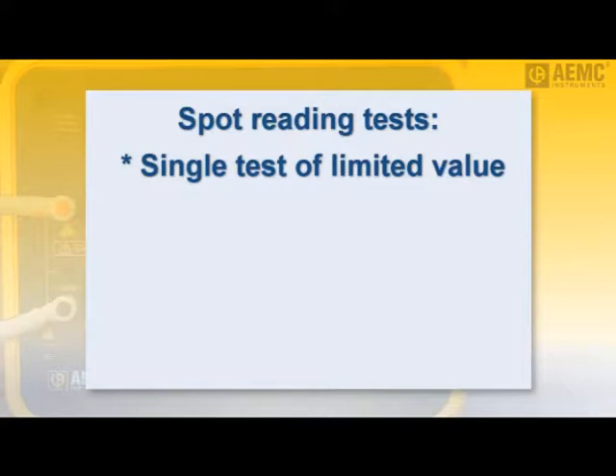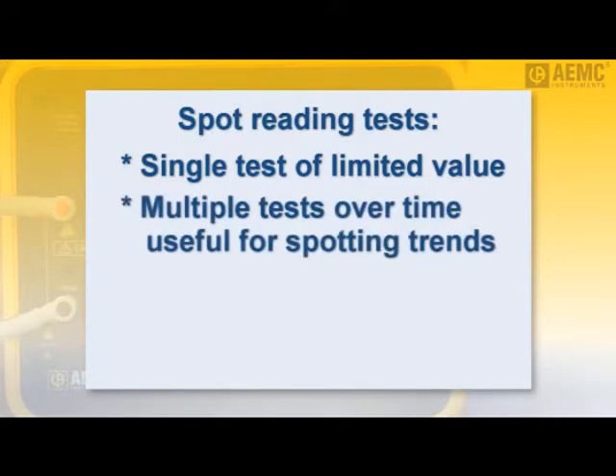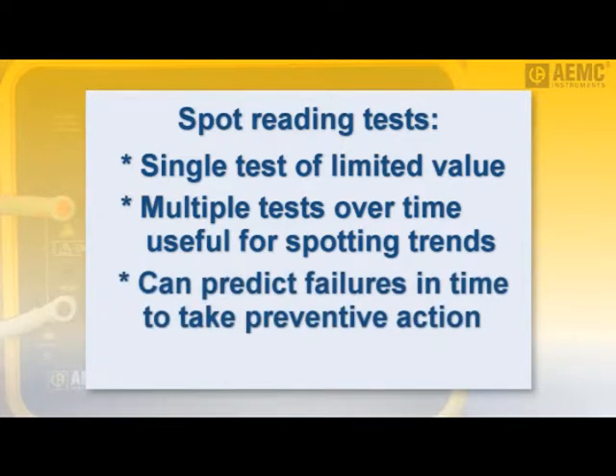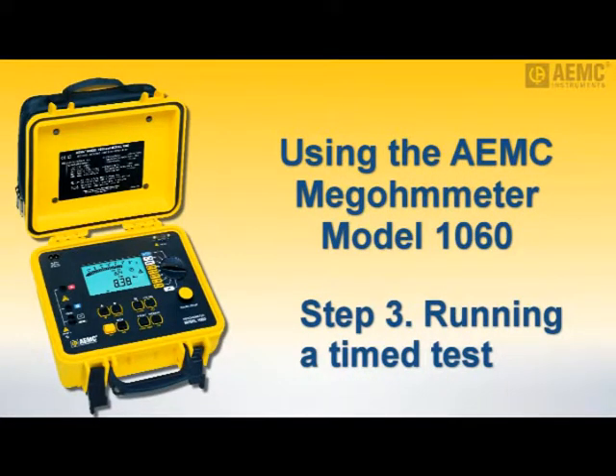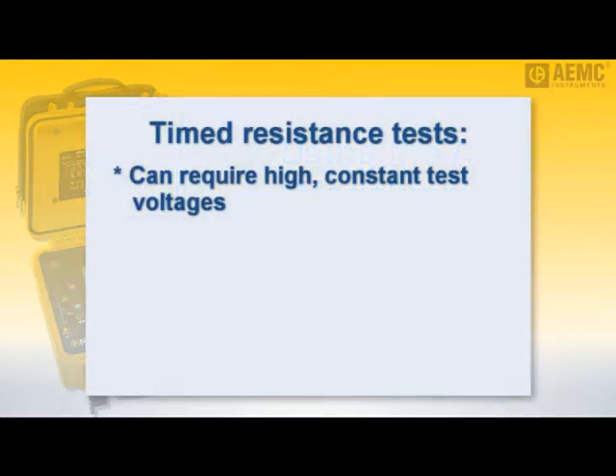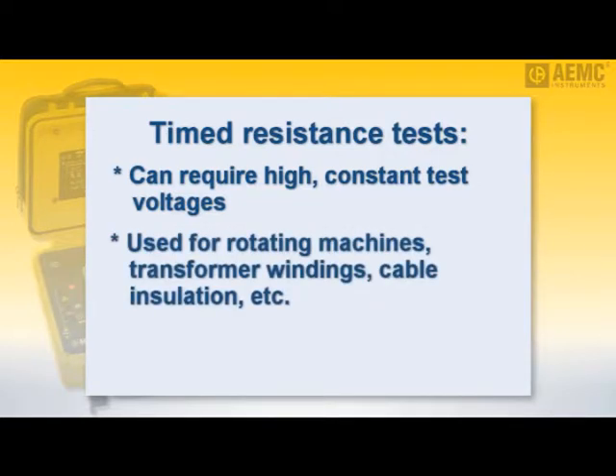Note that a single spot reading test is of limited value, but the results become meaningful when a series of tests — all featuring the same test voltage and duration — are performed over time and the results compared. This comparison can help predict a potential insulation failure in time to take preventive action. You can also print the measurement by connecting the instrument to a serial printer, as explained in the instrument's user documentation. Now we'll demonstrate a more complex insulation resistance measurement method known as the timed resistance test, which involves configuring the test to run for a defined period of time. This test is particularly useful for large rotating electrical machinery, especially systems with high operating voltage, as well as for measuring resistance in transformer windings and cable insulation.